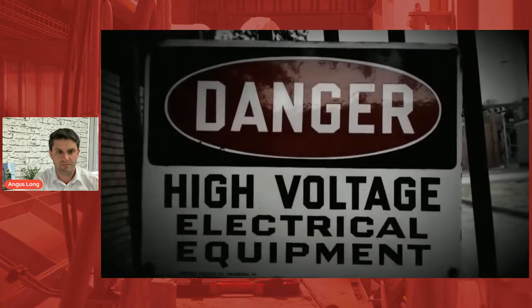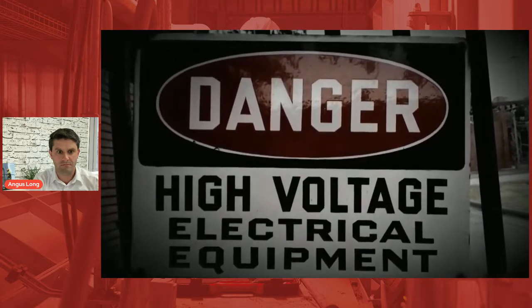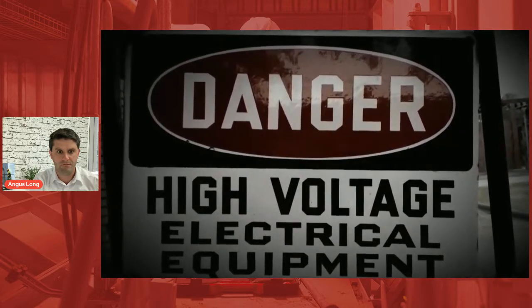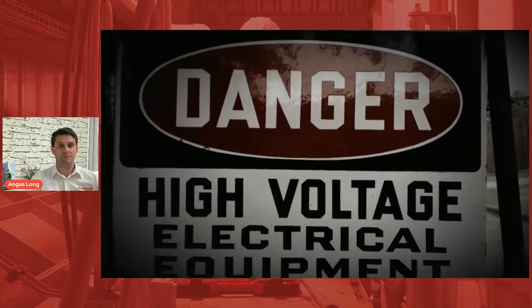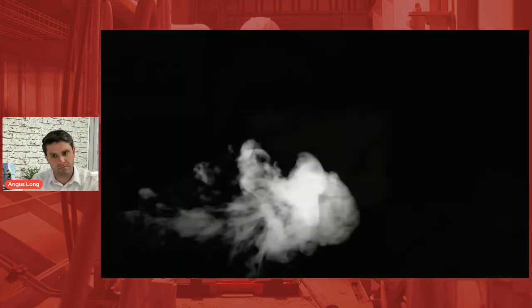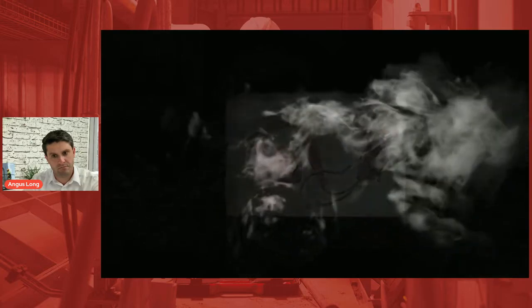After I tested the generator power, I went into the main building electrical to test it. I opened up a small panel for their main switchgear, the main breaker panel for the entire building. I clipped A phase with one alligator clip, then B phase, and as I went to clip C phase, the meter blew up and blew a puff of carbon into the electrical box.